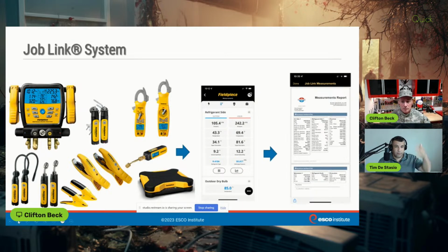Years ago, we checked airflow with the handometer, felt good coming out of the vents. Maybe we checked to make sure our blower wheel wasn't dirty, our filter was clean, our indoor coil was clean, but we had no accurate way of quantifying airflow without getting a flow hood or traversing the duct or something like that, time consuming and still a lot of potential for error. Now on the residential side, we have things like TEC's True Flow Grid that you can stick in a filter grill and you've got your airflow right there. It takes less than 5 minutes to get that very accurate reading. We have things like MeasureQuick that talks to these digital tools. It talks to that True Flow Grid so that we can quantify the capacity of the system.